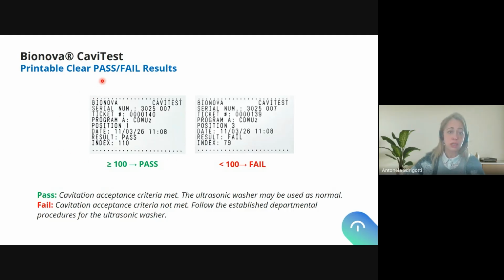In the ticket, you will have, as with any of our machines, the identity of the auto reader, in this case a Bionova CaviTest, the batch and serial number of the device, the ticket number from 0, the first incubation, and it is cumulative. The program being used, in this case, nowadays, we only have one activated program for both indicators. Of course, the position being used for the reading, the date and time of the readout, the result, if it's a pass or a fail, and of course, the cavitation index I have just mentioned.